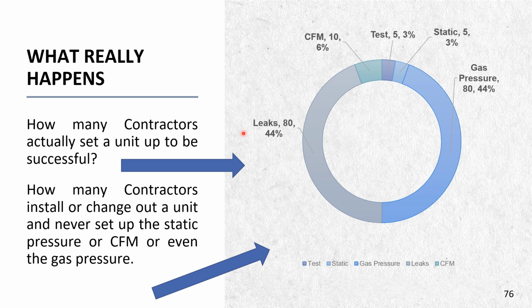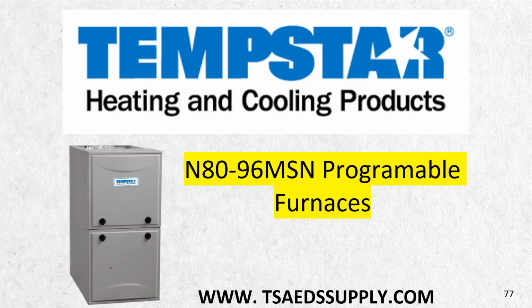And you'll have a lot of people that will test for the leaks in the lines and all that. You'll have half the people do that. And then half the people will set the gas pressure when it goes off. These are things that I run into in the field that I see are not being done. So when you look at a unit and you want to know, well, this equipment don't work, it don't do this, it's because it wasn't properly set up right. ICP requires that you properly set every unit up to where that unit is successful, so that the customer has a successful experience, and then you look good to the customer.